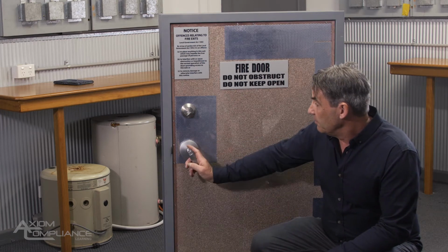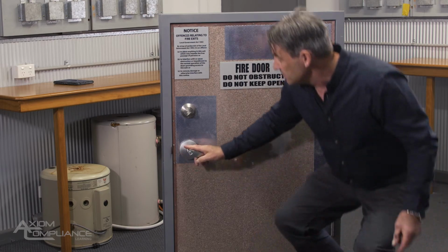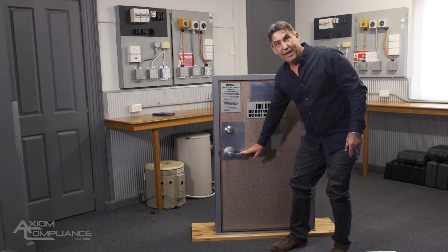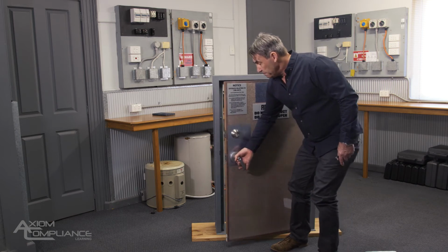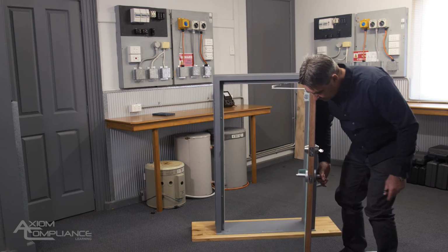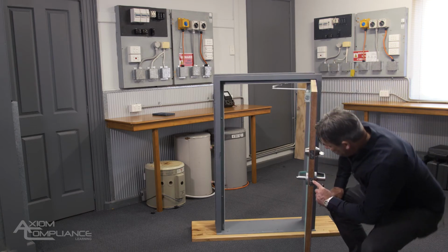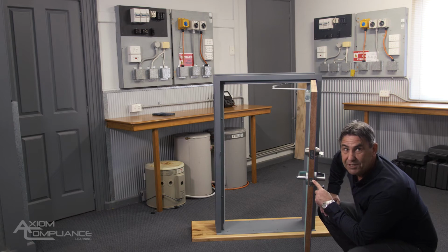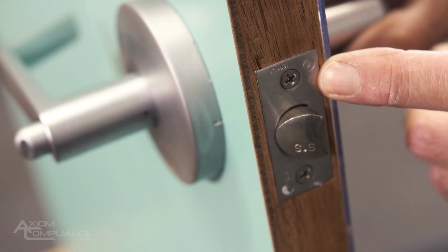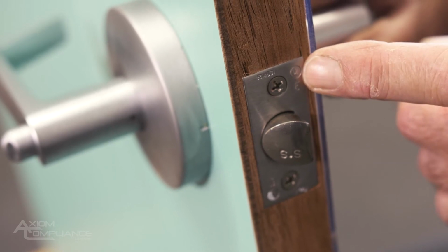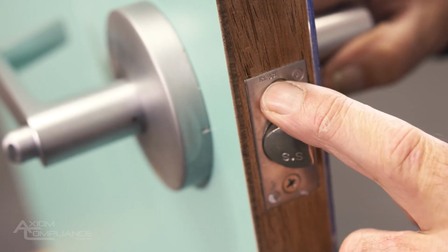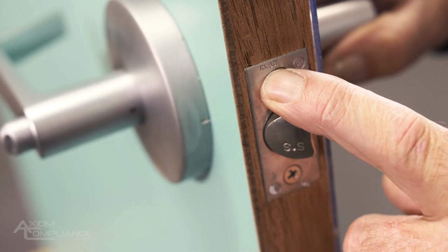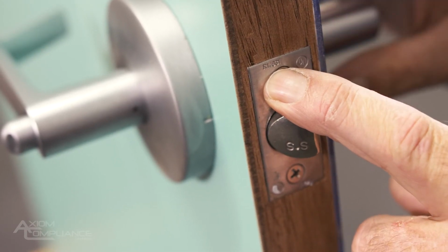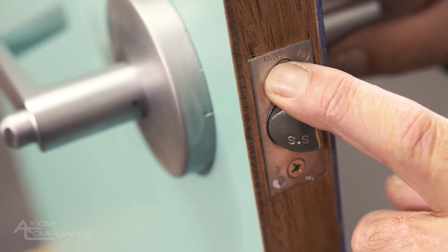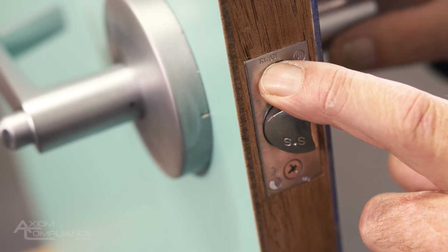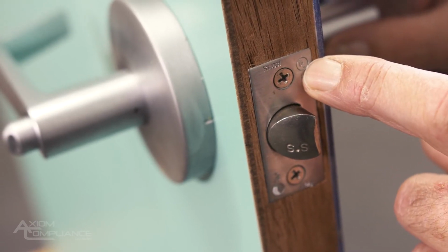Now, to determine if it's a fire door handle, I'm going to need to open the door because it's very difficult to find the manufacturer's marking on the actual handle itself. So I'm going to open up the door and I'm just going to check. Oftentimes you can see the information here. And I can see that I've got a marking F, which means it's fire rated. This F indicates it's a fire rated door set, lock set. The manufacturer is UL, and there's a model number that we can reference back with the manufacturer and to the door manufacturer as well. So the lock set manufacturer will confirm it's a fire rated door lock, and then the manufacturer of the door will confirm that that particular manufactured door set is for this door.